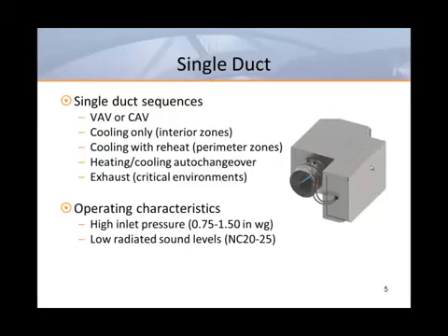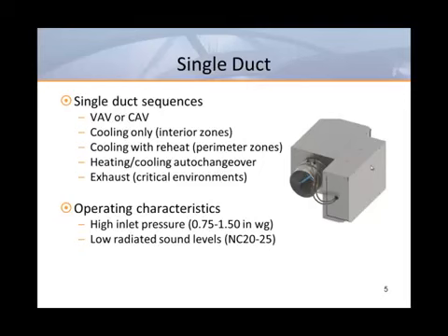Most single duct boxes, regardless of manufacturer, use the same round inlet and rectangular outlet configuration. This design reduces the inlet pressure requirement due to the static pressure regain that occurs when the air expands to fill the rectangular cabinet. The only real differences that distinguish between most manufacturers are lining options and inlet sensors. Multipoint center averaging sensors are preferred because they can provide improved accuracy with poor inlet conditions. Although single duct boxes have very low pressure requirements, the addition of reheat coils, especially multi-row water coils, can result in inlet pressure requirements as high as 1.5 inches of water.